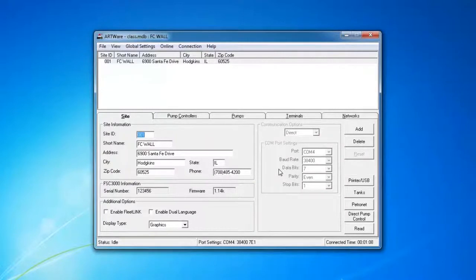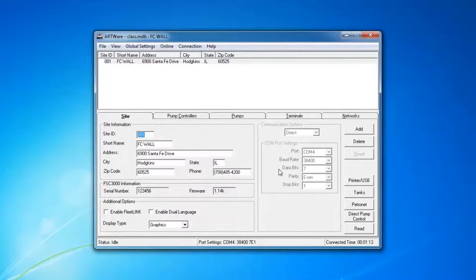But if you're changing version numbers, the software is going to cold start and all of the settings are going to be erased. So you have to make sure that you save them like we did in the previous step.